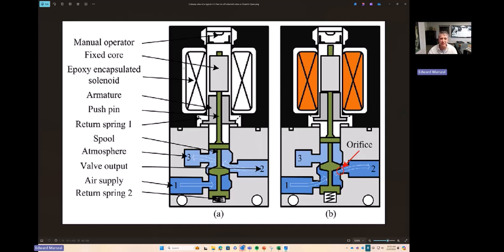Now, for that failure mode, is it just a number that you can get out of a Bellcore database? Well, that's what is going to happen when you get an FMEDA. They're going to have to pick a number for how often that coil fails. But is that number constant? Is it an inherent property of that piece of equipment? No, it's not.